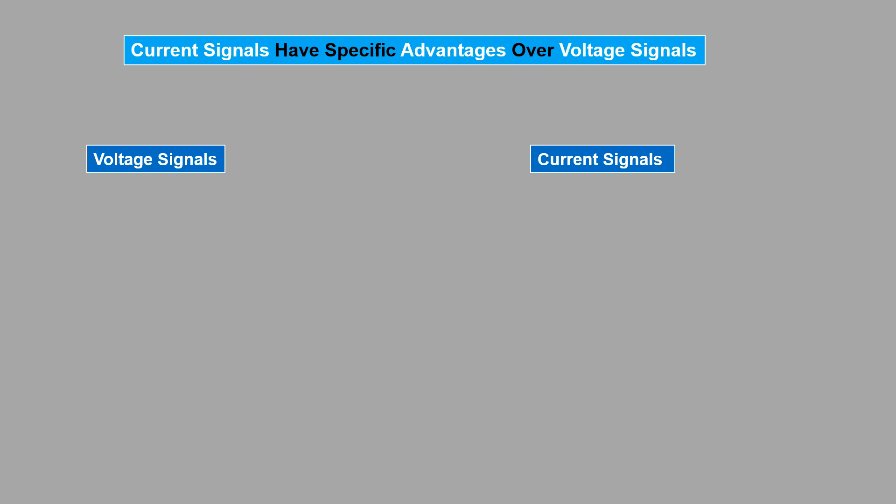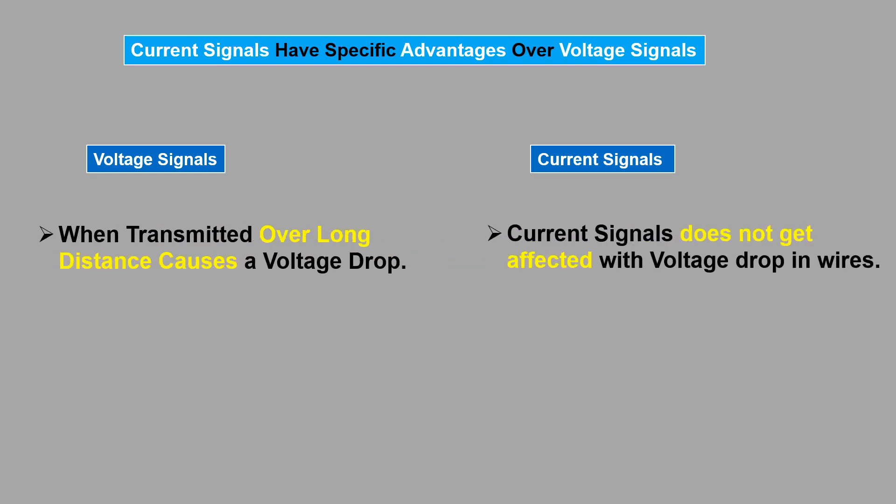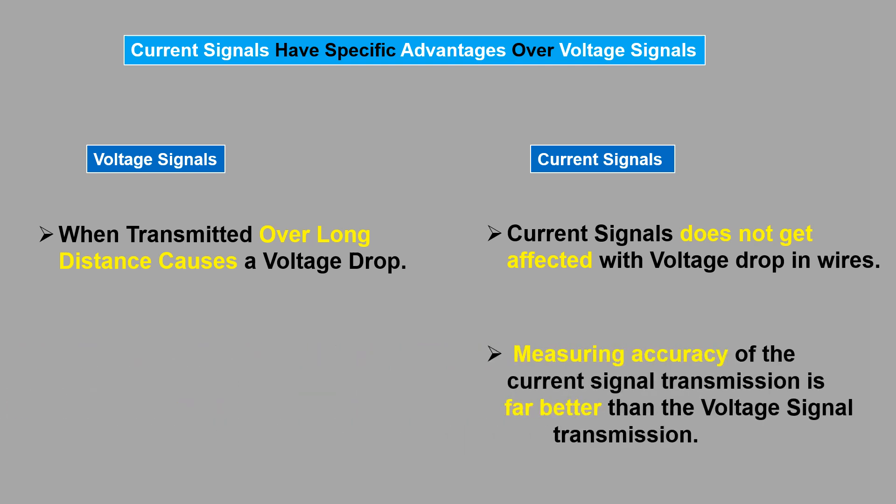Voltage signal when transmitted over a long distance causes a voltage drop in the wires. On the other hand, current signal does not get affected with voltage drop in the wires. The measuring accuracy of the current signal transmission is far better than the voltage signal transmission.